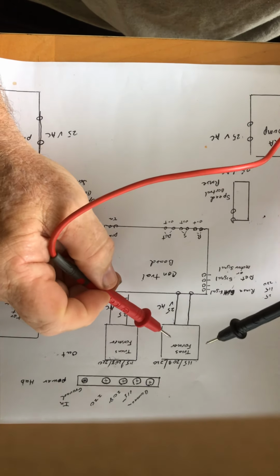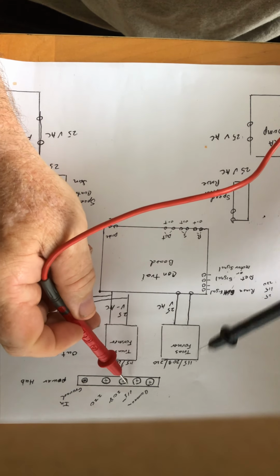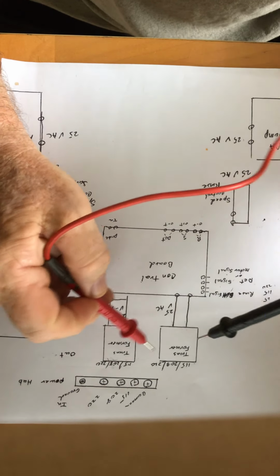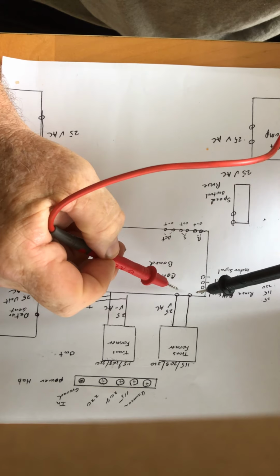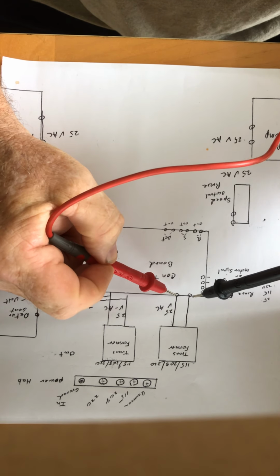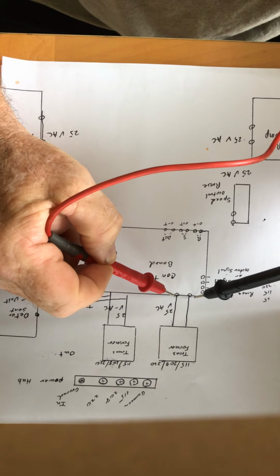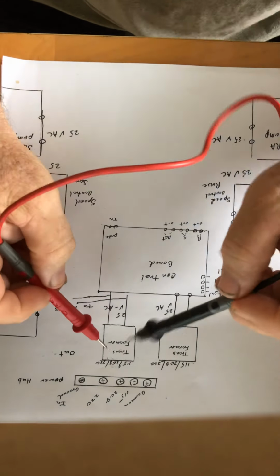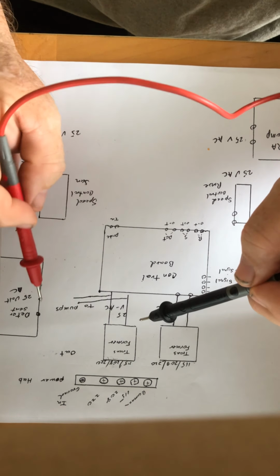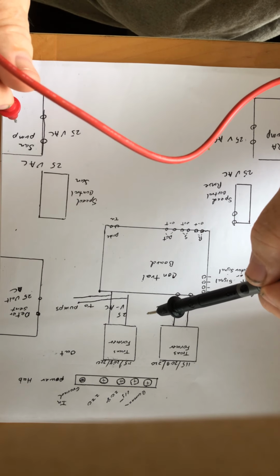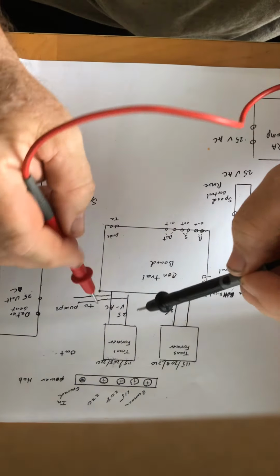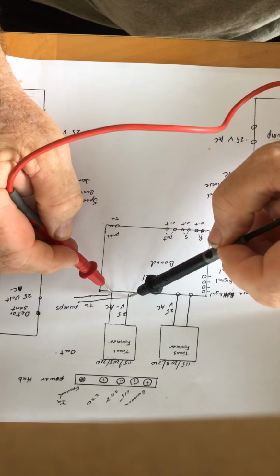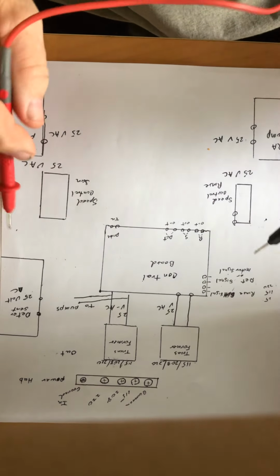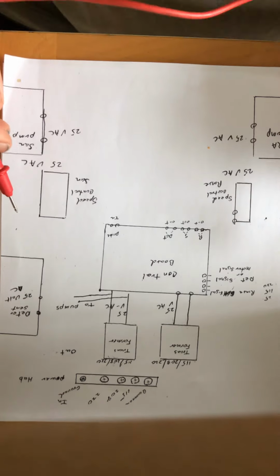Then once you get your power going to the transformer at 220 that you already verified up here, you go to the transformer, you measure it coming out. If it's coming out at 25 volts, your transformer is working fine. If your other transformer, which usually powers your accessories such as your detergent, or your sanitizer pump, or your rinse aid pump, you go ahead and hook to over here. If it reads 25 volts, you've got good power going to your accessories.